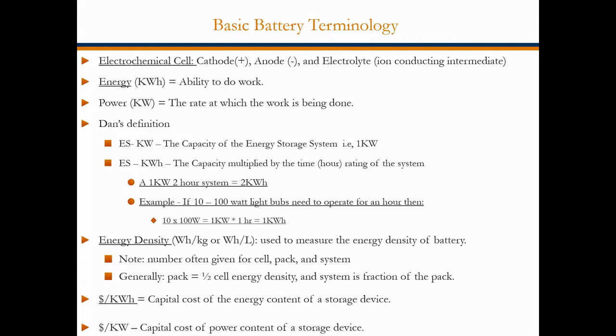A kilowatt hour is the capacity multiplied by the time and hours rating of the system. So if you have a 1 kilowatt, 2 hour system, you have a 2 kilowatt hour system. As an example, if you have 10 100 watt light bulbs that need to operate for 1 hour, then you would need a 1 kilowatt system for 1 hour, and that would be a 1 kilowatt hour system.